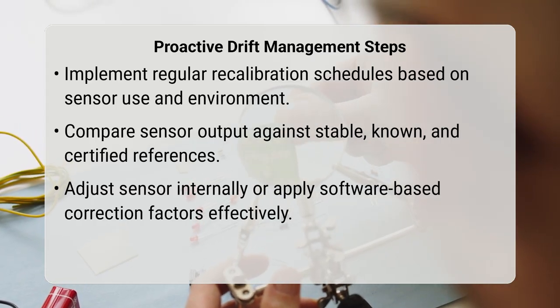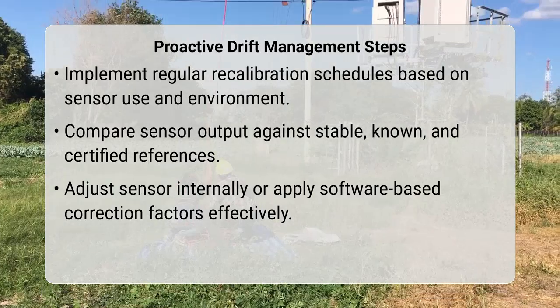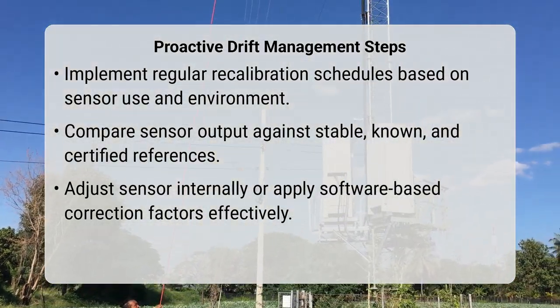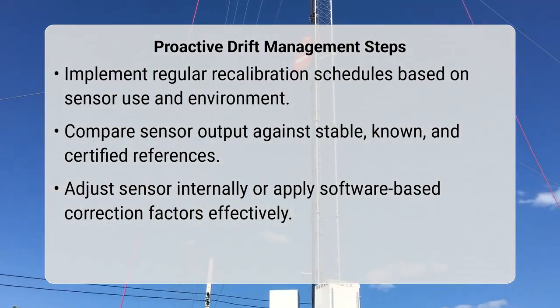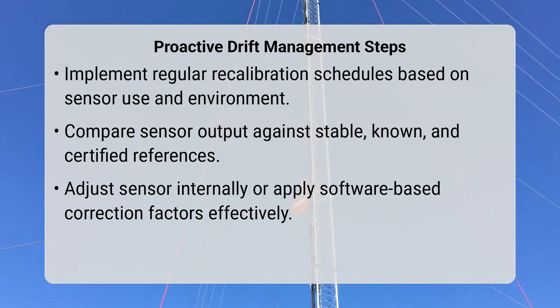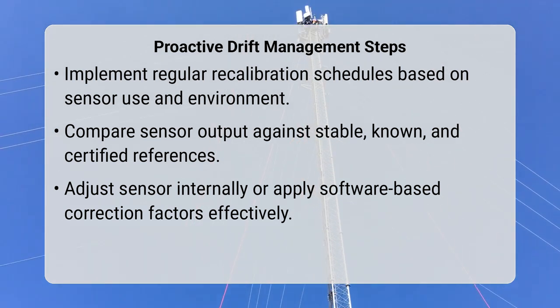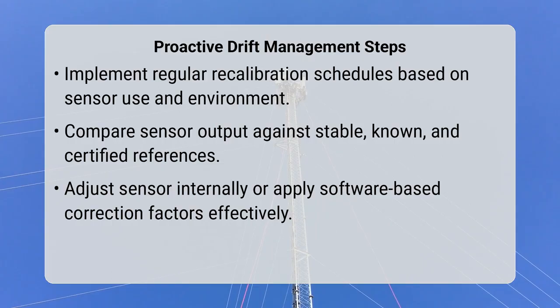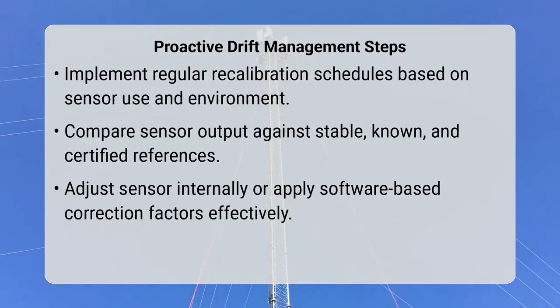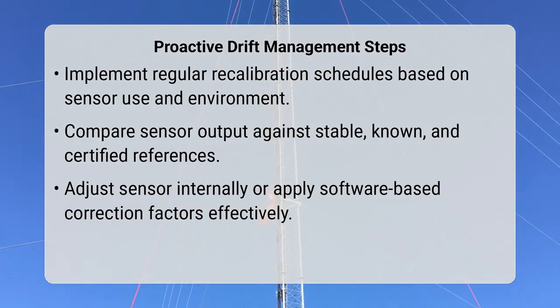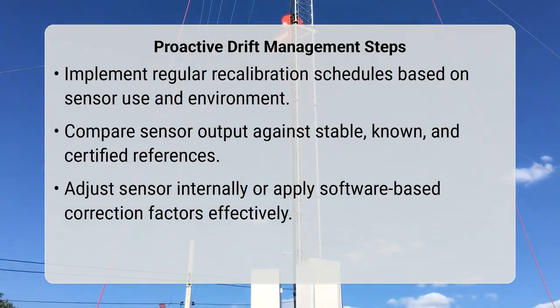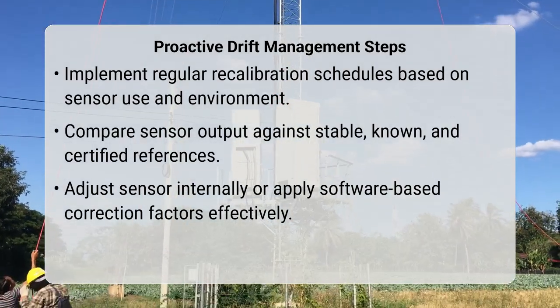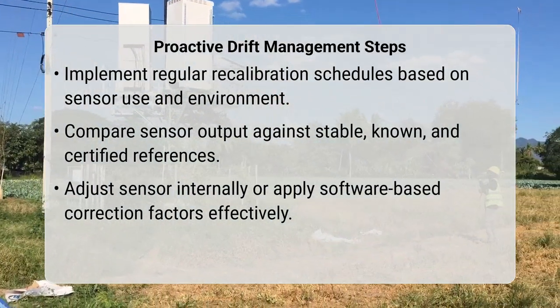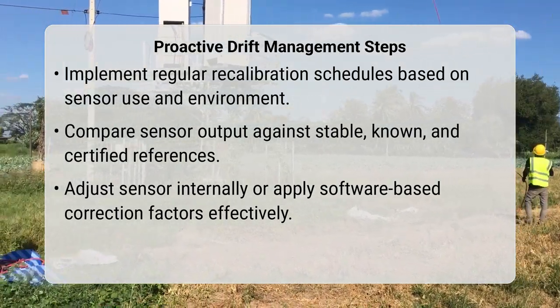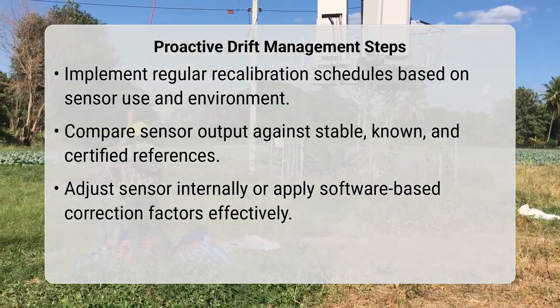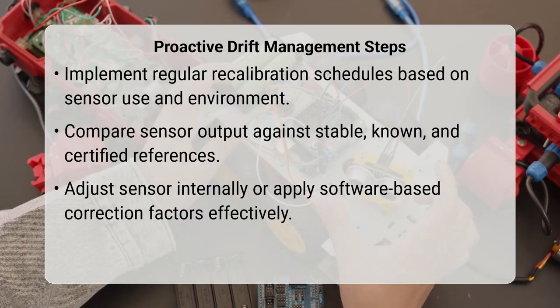This deviation is subsequently compensated for, either by adjusting the sensor's internal electronic parameters or by applying a software-based correction factor within the larger system that interprets its readings. This proactive and systematic approach effectively prevents the uncontrolled accumulation of measurement error. Understanding and actively managing sensor drift is a cornerstone for ensuring the long-term stability and trustworthiness of any measurement system.